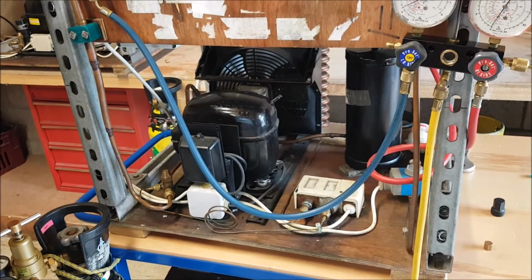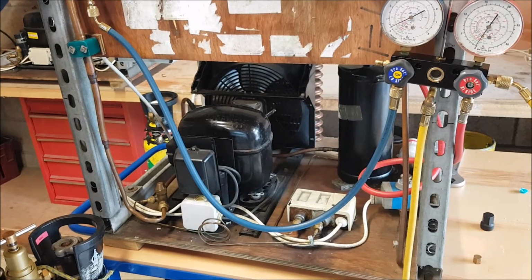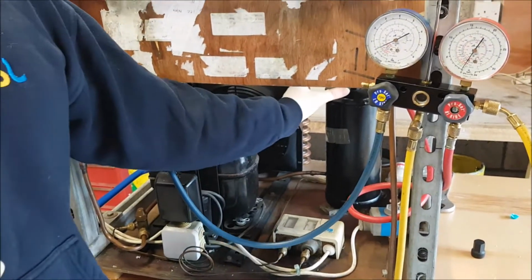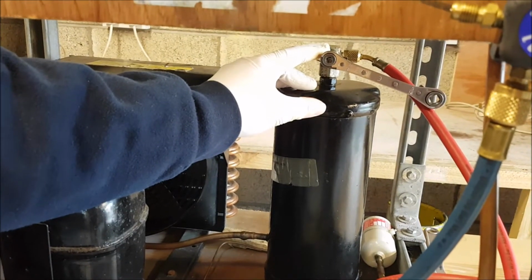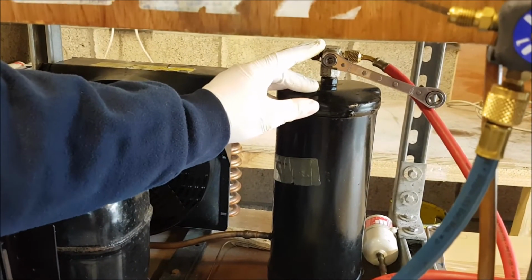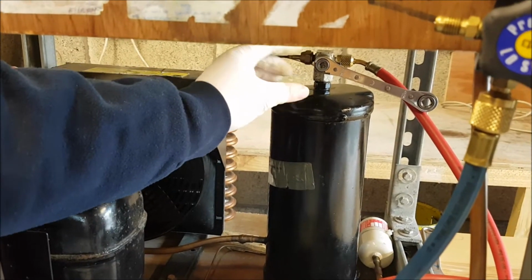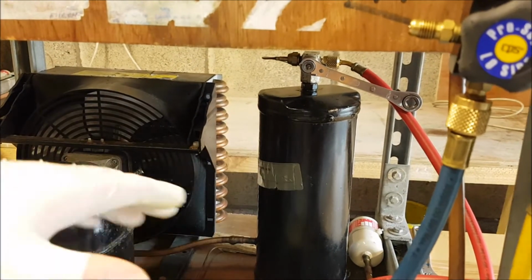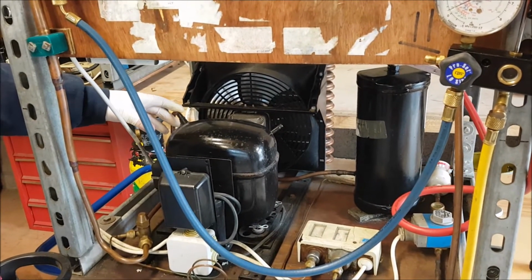The reason why I am labouring on repairs that force us to remove refrigerant is because, going back to the video that explained how our access service valve works, we have the capacity of fully front seating this valve. By fully front seating the valve, we can store all the refrigerant in the liquid receiver, in the liquid pipe as far as the condenser, in the condenser, and as far as the discharge side of the compressor.